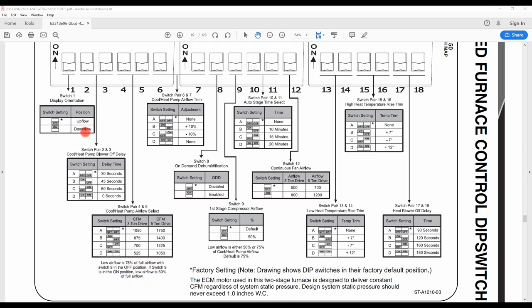If you're an upflow application, yet you turn it on, then it flips your dip switches. It turns your diagnostic codes over. So your diagnostic code of a 59 will actually look like a 56 at that time. And then you will be calling into us asking what code is a 56. We do not find that anywhere in our books. So do verify that first dip switch is set for an upflow or downflow application. They did it more for ease of service, for you to easily see the error codes. That's all dip switch number 1 does.